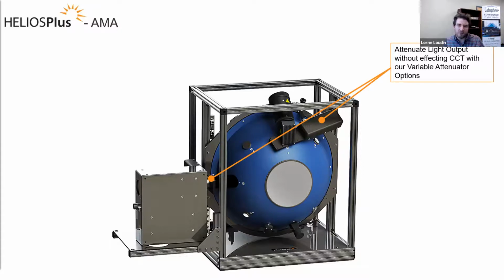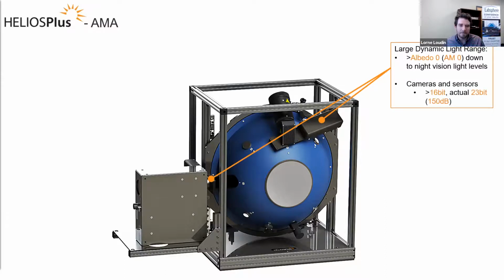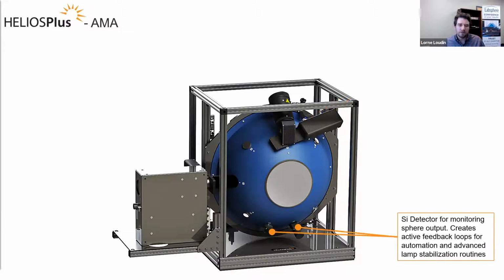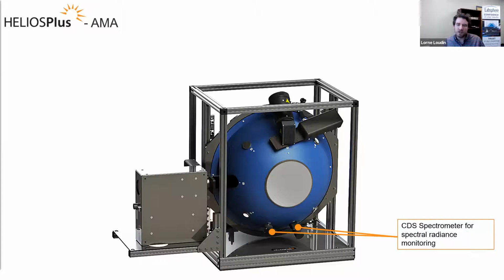And so one of the features of a lot of LabSphere's Helios Plus systems is the ability to adjust the light level at your exit port by attenuating your signal on a variable attenuator. This allows you to change your light level without affecting the color temperature of the outgoing light. And again, you get some really nice dynamic range on this system. And you're monitoring the output with a silicon detector. And that also is used to provide a feedback loop in the software that allows for some stability measurements. In addition, the spectral output of this system is monitored with one of our CDS spectrometers.